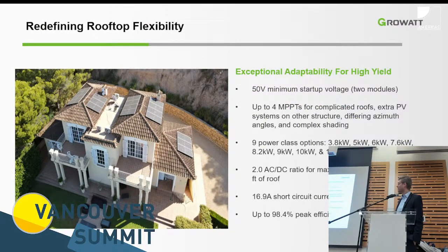One of the features Growatt is advertising is that they can have a very, very low string voltage. It can go all the way down to 50. This is the inverter that has the lowest starting voltage in the industry. That sounds like a big sales pitch, but with every transformerless inverter, the target is always to have the strings as long as possible, because that's where the system is efficient. That's where you have the boost converter not continuously boosting a very large voltage gap, and a 50-volt string is not really a string. It's probably just two modules in series. That doesn't make a lot of sense to design, but electrically that can be used.